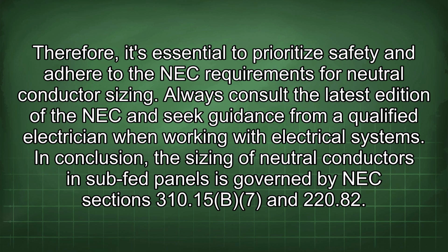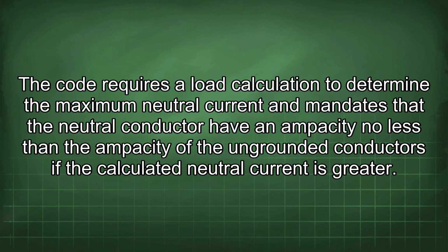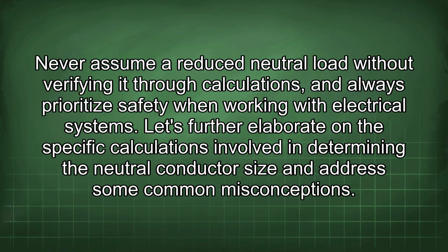In conclusion, the sizing of neutral conductors in sub-fed panels is governed by NEC sections 310.15(B)(7) and 220.82. The code requires a load calculation to determine the maximum neutral current and mandates that the neutral conductor have an ampacity no less than the ampacity of the ungrounded conductors if the calculated neutral current is greater. Never assume a reduced neutral load without verifying it through calculations, and always prioritize safety when working with electrical systems. Let's further elaborate on the specific calculations involved in determining the neutral conductor size and address some common misconceptions.